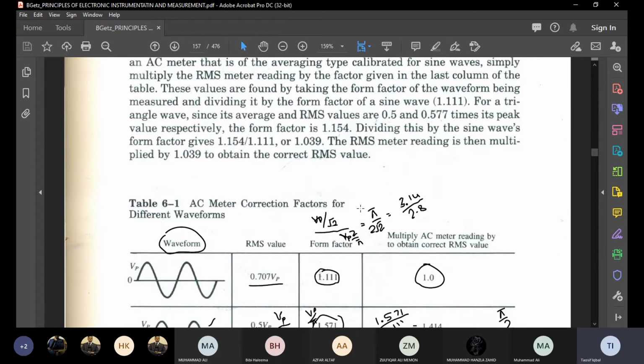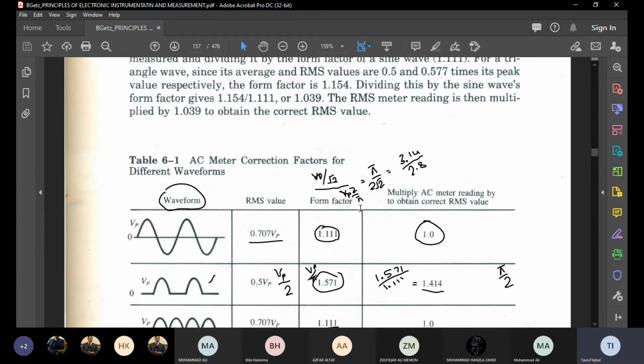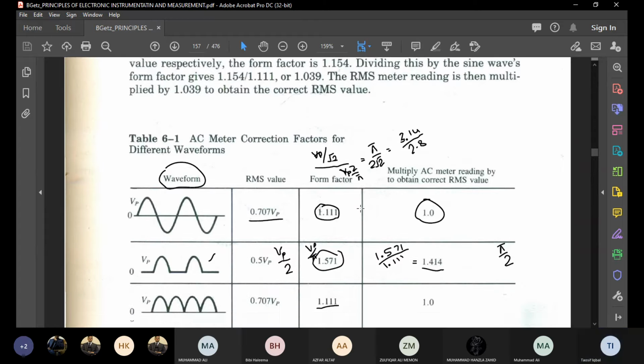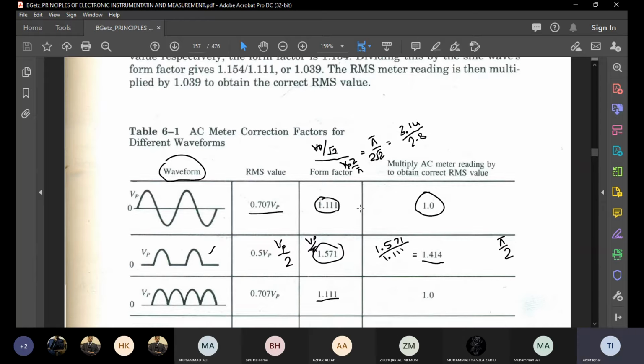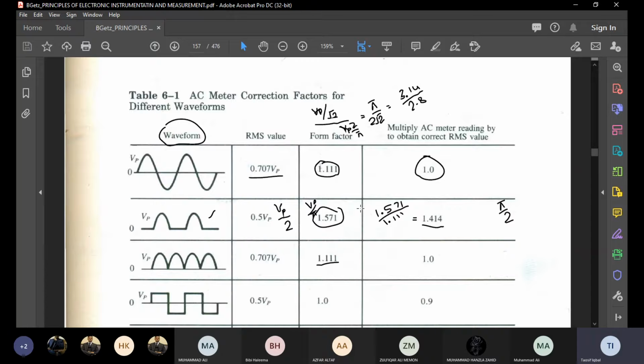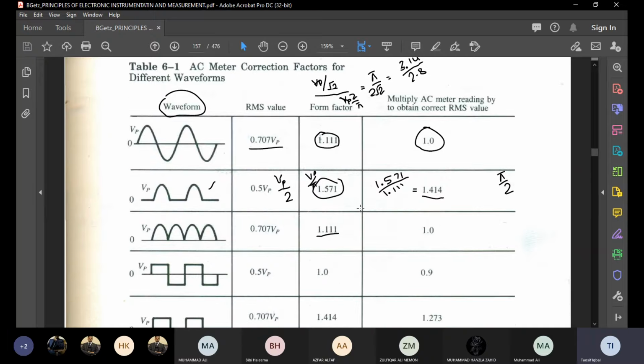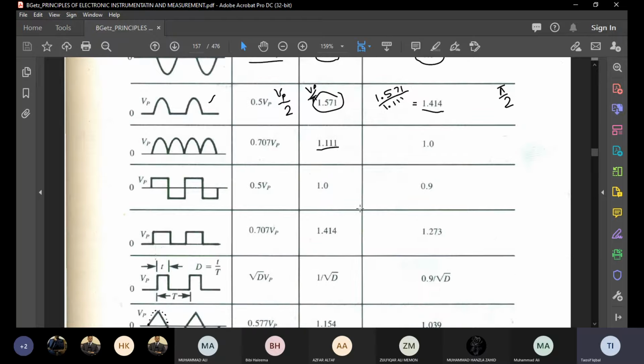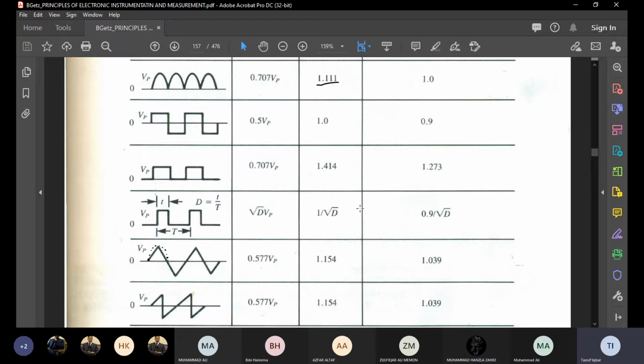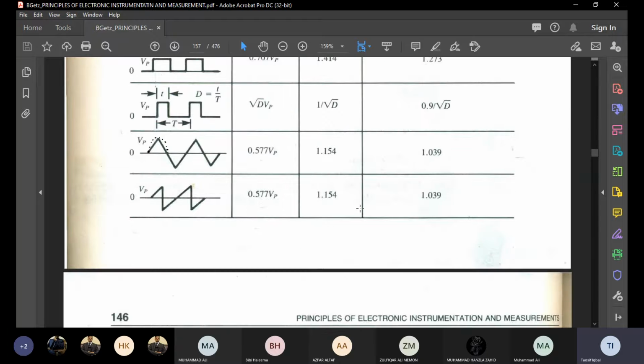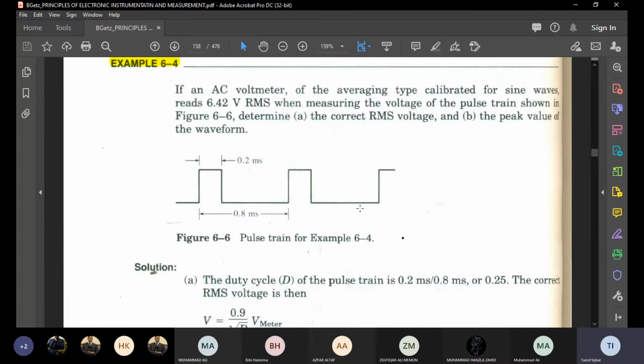Similarly, all these meters are basically tuned to have a single type of waveform, maybe we tune it for a sinusoidal waveform. To measure other types of waveforms and their signals, we have to use some tuning factor or correction factor if the waveforms change from sinusoidal to non-sinusoidal. Then you just multiply the meter reading with this factor and get the correct value for the certain waveform.